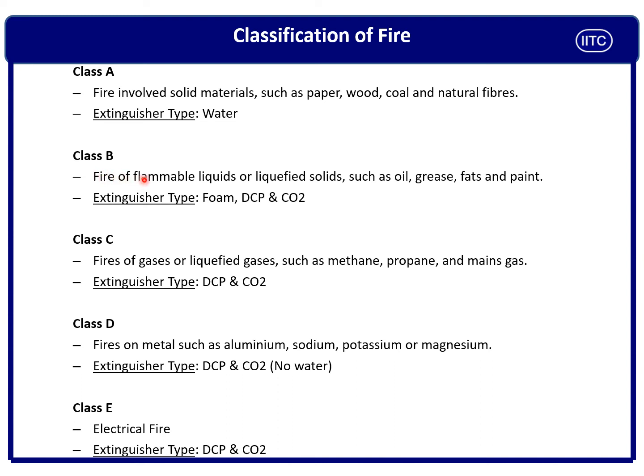Class B fire involves oil, grease, fat, paint, and liquid fuels. To extinguish Class B fire, we use the blanketing effect or starvation — using foam. The foam creates a blanket over the liquid to cut off oxygen from the fire triangle, thus breaking the triangle.